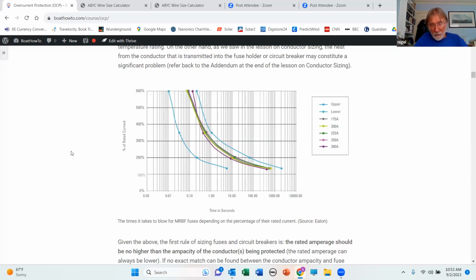The reason we don't put it in cranking circuits is because typically speaking, if you looked at the voltage drop on the cranking cable, you would find it's over 10%, because starter motors are very tolerant of voltage drop. We're not worried about the conductor heating up, even if the ampacity of the conductor is below the amp draw of the starter motor, because we're only running the starter motor for a second or 2. Worst case, 10 or 15 seconds. So the conductor, even if it's undersized, is never going to get hot enough to melt down. If we stick a fuse in that circuit based on the ampacity of the conductor, every time we crank in cold weather, we're going to blow the fuse.